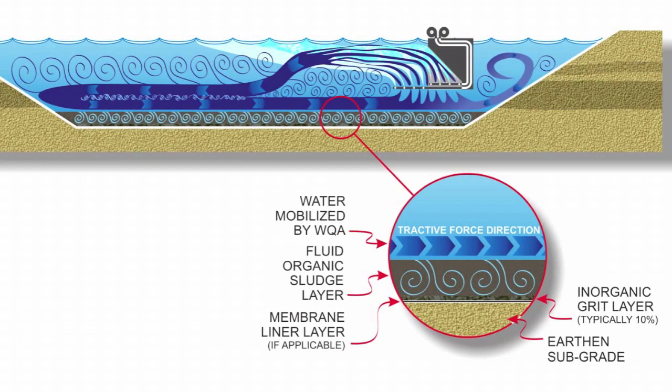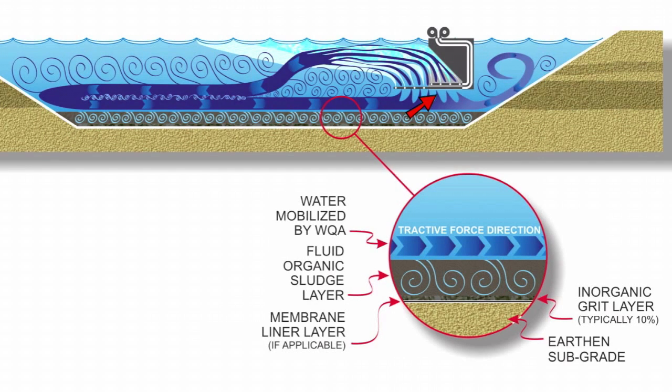A side view of the lagoon aerator clearly visualizes the unique utilization of bubbles to perform these important functions. A single 2 horsepower regenerative blower provides the air which lifts over 9 million gallons of water per day through the unit. By deflecting these coarse bubbles against an inclined baffle, the water is set in motion at a very fixed and slow forward movement, approximately 25 feet in front of the aerator. The forward-moving water can no longer move on the surface due to the pressure of static mass of lagoon water, so with continuous pressure from behind, the water falls to the lagoon bottom.